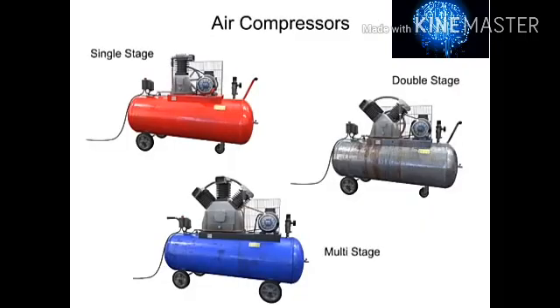If pressures of more than about 175 psi are needed, multi-stage compressors should be used. On these larger compressors, cooling may take place by circulating water instead of air. To reach a pressure of 2500 psi, as many as 6 or 7 stages may be needed with cooling between each stage.